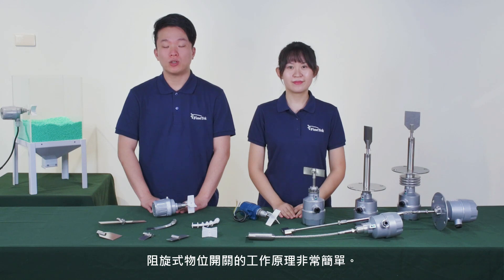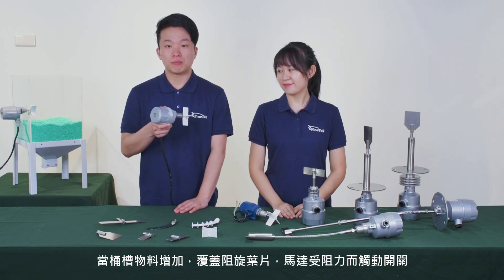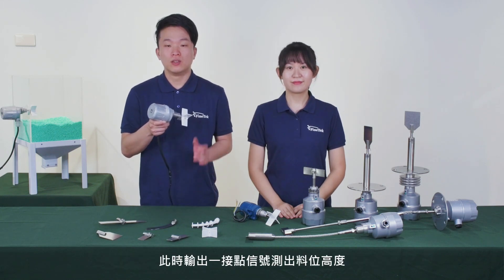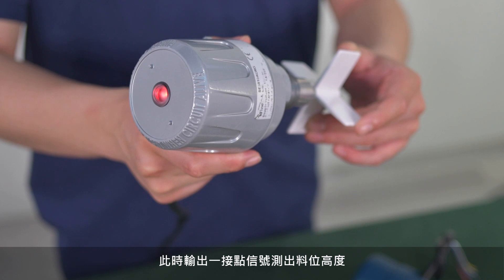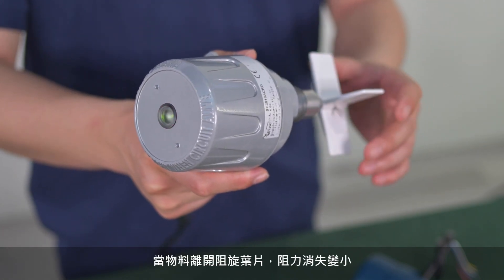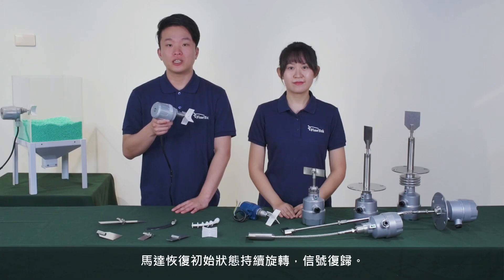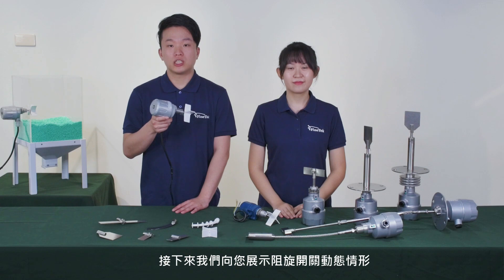Therefore, it is recommended to use it with granules or powder whose specific gravity is equal to or larger than 0.3 grams per cubic centimeter. The working principle of the rotary paddle level switch is very simple. When the material in the tank increases to impact or surround the paddle, the motor will stall and cause the micro switch to indicate an alarm or control.